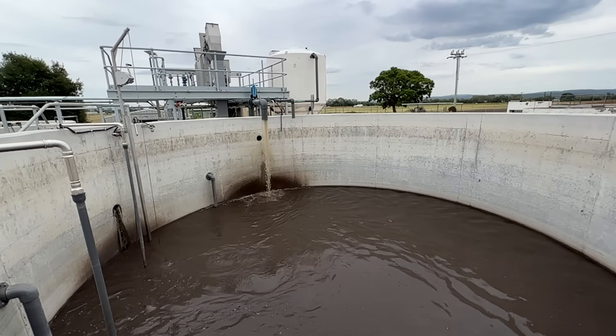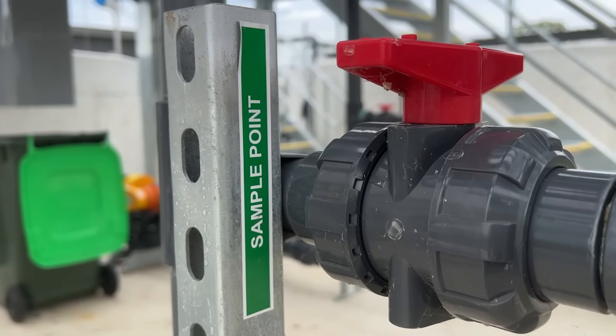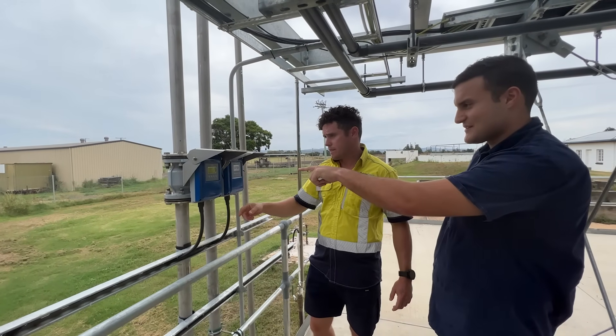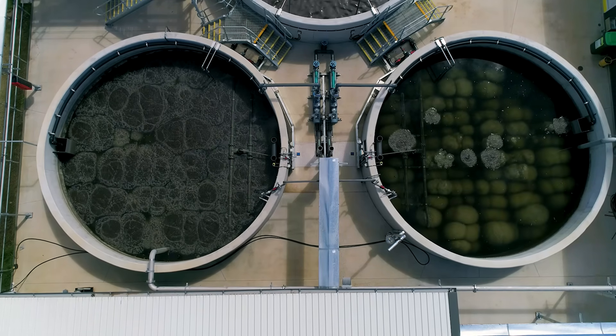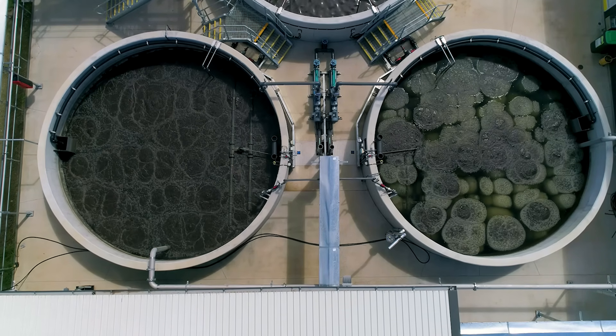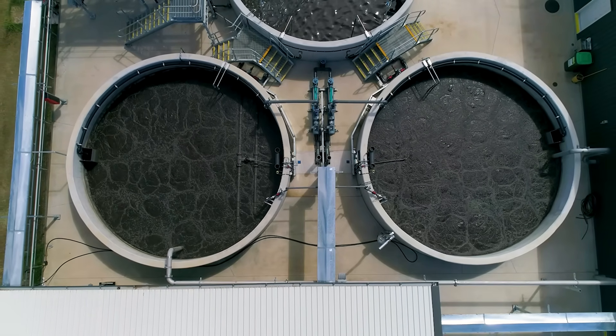The plant's been performing well. We just got the recent results and it's getting two milligrams per litre BOD, which is very good, and also eight milligrams per litre suspended solids. It's completely removing ammonia, which is really great, and very low nitrate and phosphorus — so it's going better than expected, really.